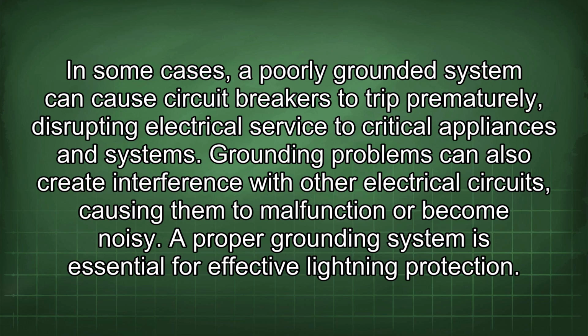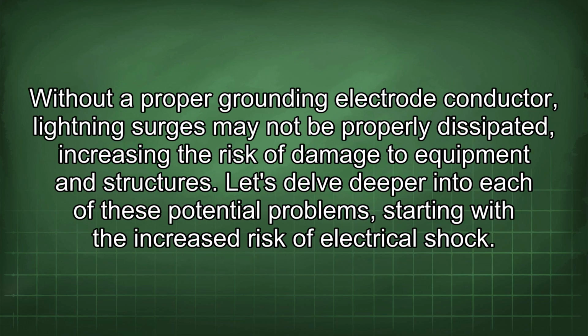A proper grounding system is essential for effective lightning protection. Without a proper grounding electrode conductor, lightning surges may not be properly dissipated, increasing the risk of damage to equipment and structures. Let's delve deeper into each of these potential problems, starting with the increased risk of electrical shock.